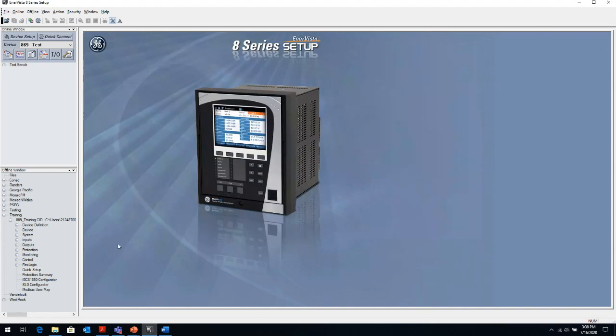So once I've done that and I save that, I basically set up my relay to trip for those elements, and I'm basically done as long as I've set up my oscillography properly. Now, if you're looking at an existing setting file and you want to see what protection elements are enabled, an easy way to get to that is from the protection summary, right below the quick setup.